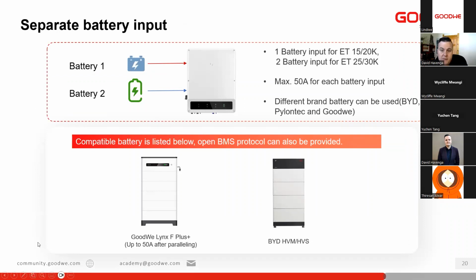And then we have the separate battery inputs. So let's talk about that. The 15 and the 20 have one battery input. The 25 and the 30 have 2 separate battery inputs. Those battery inputs can be used in parallel, or you can have 2 completely different batteries on the inverter. If one battery is available today, let's say today the Lynx F is available, we install that. We can also parallel those batteries. And 6 months down the line or a year down the line, the customer wants to install more batteries. Either you could use another pair of Lynx F on the second input, or you can install a BYD battery on the second input, depending on what solution is available at that time. It gives you a lot of flexibility.